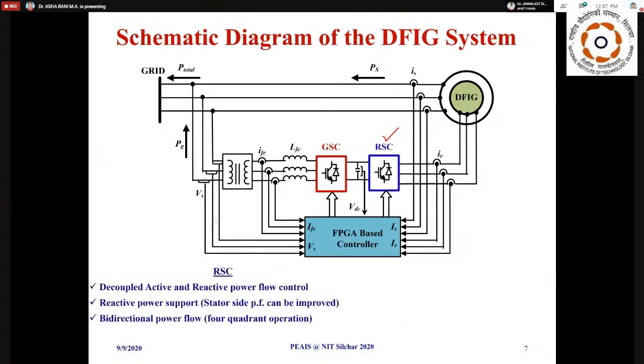So what happens here is, the rotor side converter, with the help of the capacitor, will be providing the sufficient reactive power requirement for the machine in this direction. That is possible, and that is the biggest advantage. We don't want to take anything from the grid. As we all know, whenever we are connecting anything to the grid, the important thing to be noted is we have to always maintain the power factor of the grid at unity, which means you should not consume any reactive power from the grid. That is actually possible with the help of DFIG.